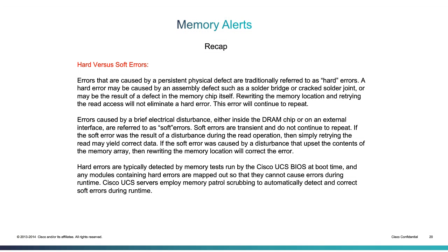Okay, and just to recap over these memory alerts, you have your hard errors and you have your soft errors. The basic rundown is when you have a hard error, this is most likely a hardware-related issue, and it will not be resolved unless it is exchanged with a working component. Whereas when you look at the soft errors, they're transient. They're not consistent, of course. Other people may consider them correctable errors. With the memory technology of using ECC memory, you are able to tolerate soft errors or correctable errors and even reset those counters so that you do not continue to accumulate them.